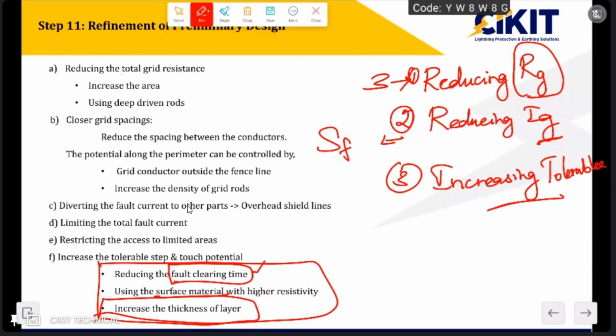And third, if I cannot make any modifications to the system to reduce this actual value, then what I can do is make some modifications to increase the tolerable limit. If I increase this tolerable limit, then I can make this design safe. They have even provided 3 steps for increasing the tolerable limit also. So by using these recommendations provided by the standard, we can ensure that the criteria of step and touch voltages are met, and we can ensure that the design is safe.